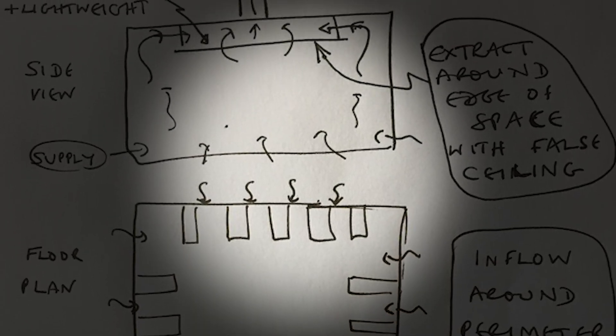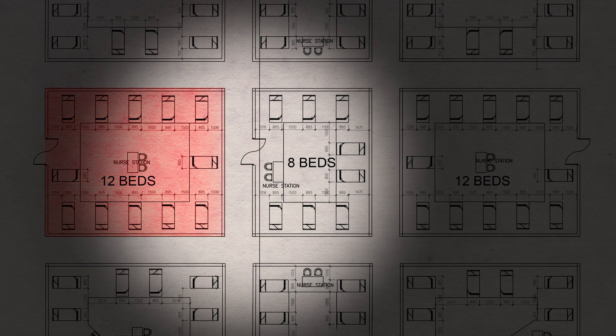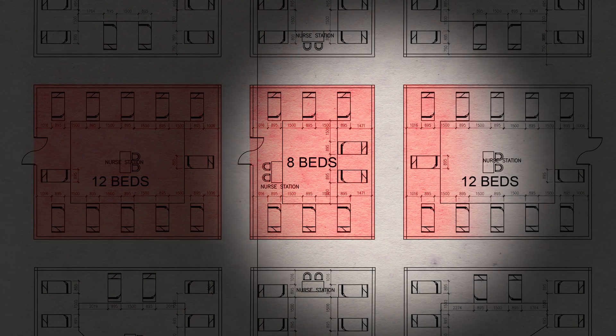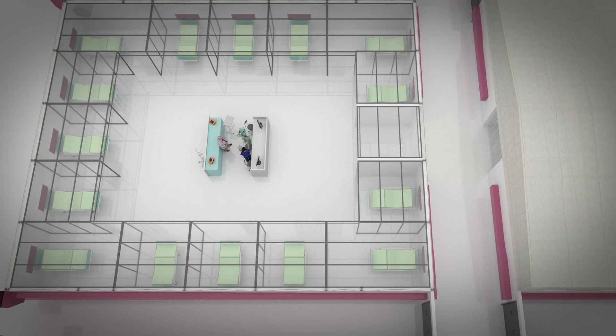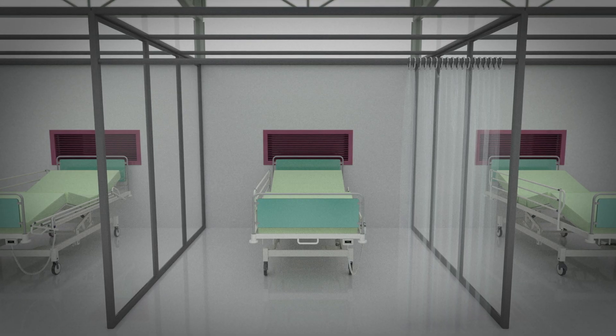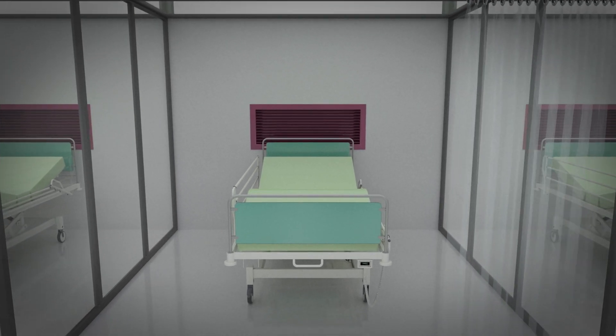Correct design and not expensive air conditioning equipment can reduce many of these cross-infection risks. The team recommends subdividing the large floor plate of a typical wide-span hall into containable enclosed patient zones, a minimum of 16 metres square, with some 10 to 20 beds, with solid partitions of up to 3 metre height and perhaps lighter clear polythene sheeting above, taped up to prevent air leaking in or out — and with it the virus.